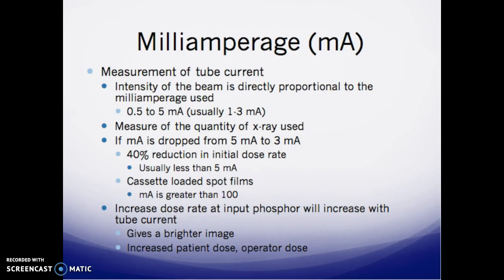If the MA is dropped from 5 MA to 3 MA, there's about a 40% reduction in the initial dose rate. With cassette-loaded spot films during fluoro, the MA is greater than 100. Increasing dose rate at the input phosphor will increase with the tube current, giving a brighter image, but it also increases the patient dose and the operator dose.